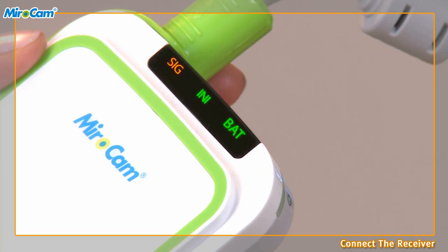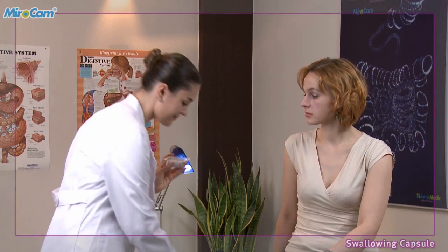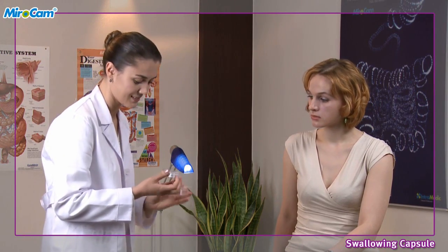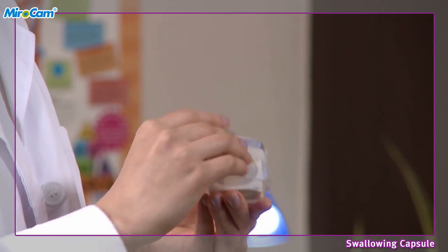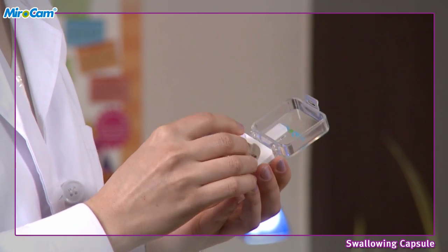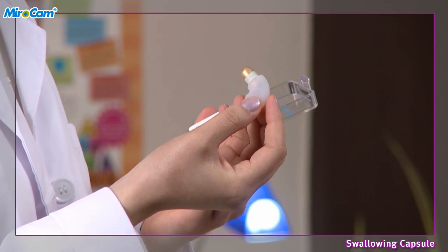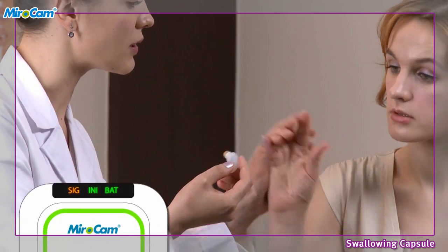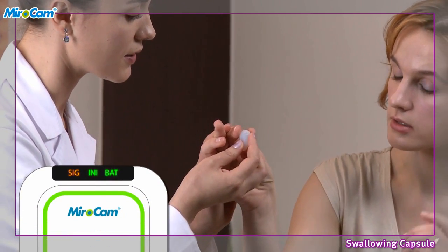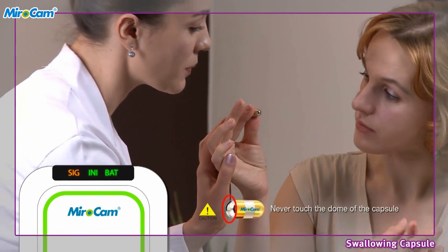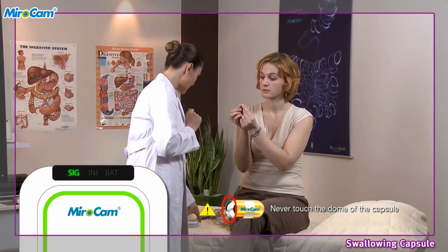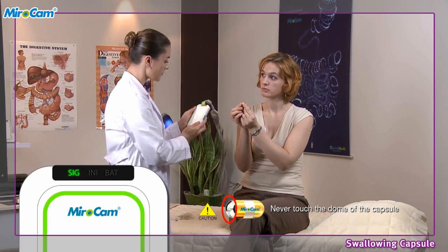If the INI indicator is orange, the receiver needs to be initialized. If the BAT indicator is orange, the battery needs to be charged. Swallowing of capsule. Open the capsule packaging and take the capsule out of the case by the opaque plastic capsule holder. Check to see if the capsule light is flashing. Instruct the patient to hold the capsule by the gold bands between the forefinger and thumb of both hands.